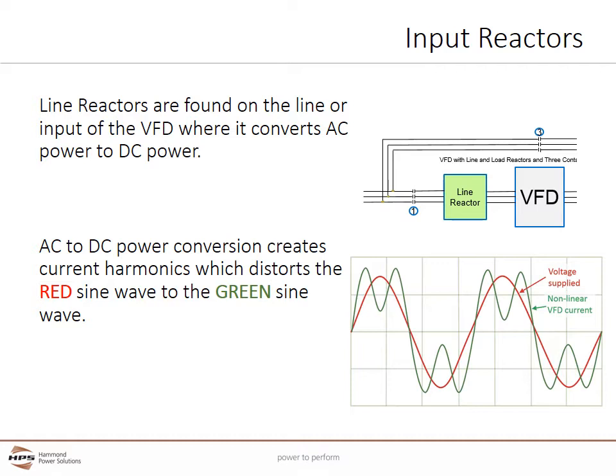Line Reactors are found on the line or input of the VFD where it converts AC power to DC power. All three AC phases energize a single common DC bus. AC to DC power conversion creates current and voltage harmonics, which distorts the perfect sine wave. Line Reactors will help to mitigate this distortion.